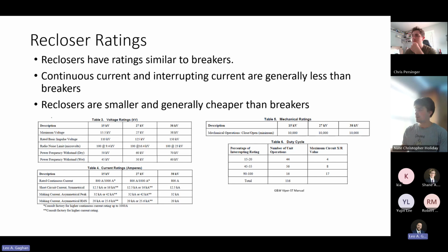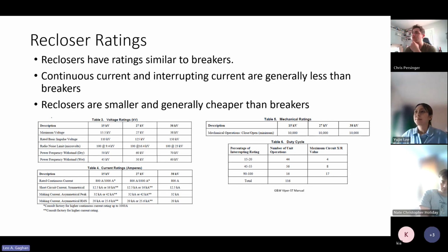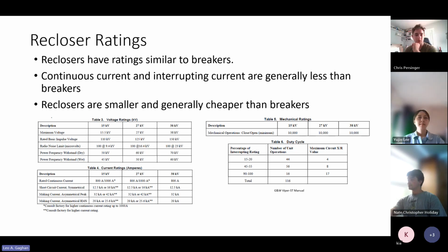So I've got these highlighted here, maybe as a comparison to a breaker. Reclosers are generally smaller and cheaper than breakers. They usually wouldn't have quite the interrupting rating of a breaker, but oftentimes they'll get the job done on a distribution system. So they're pretty common.